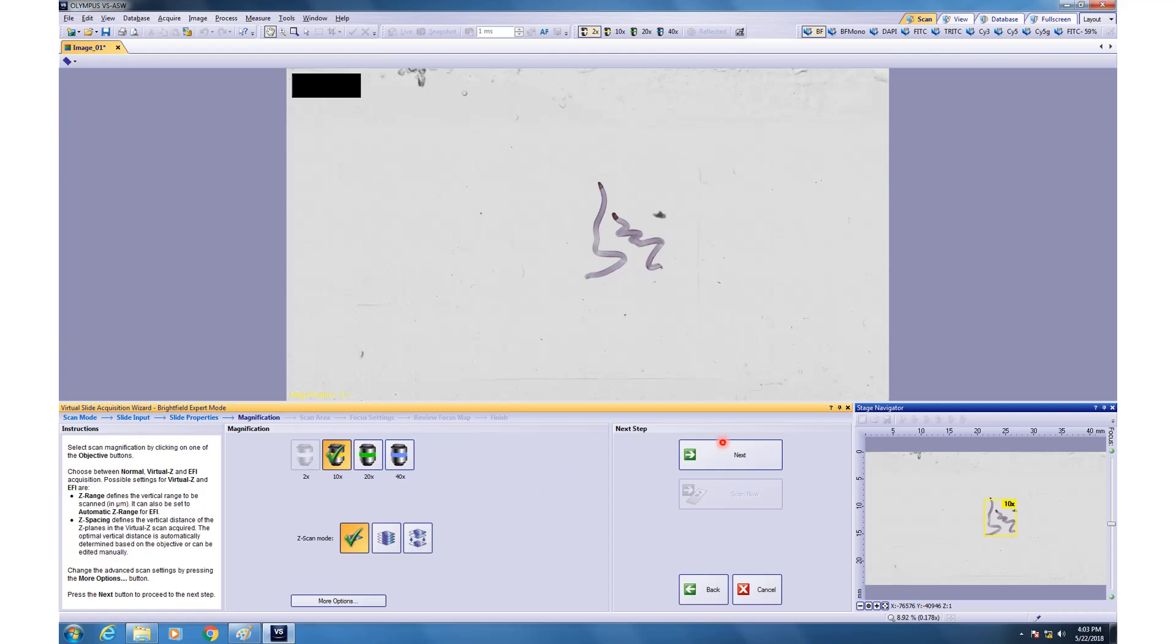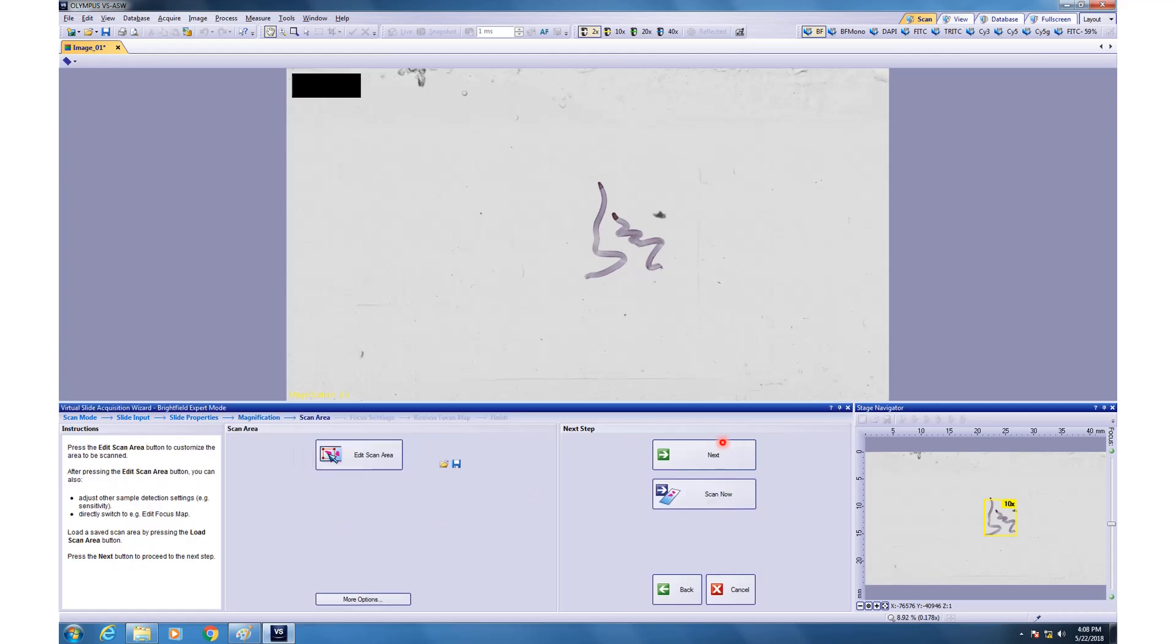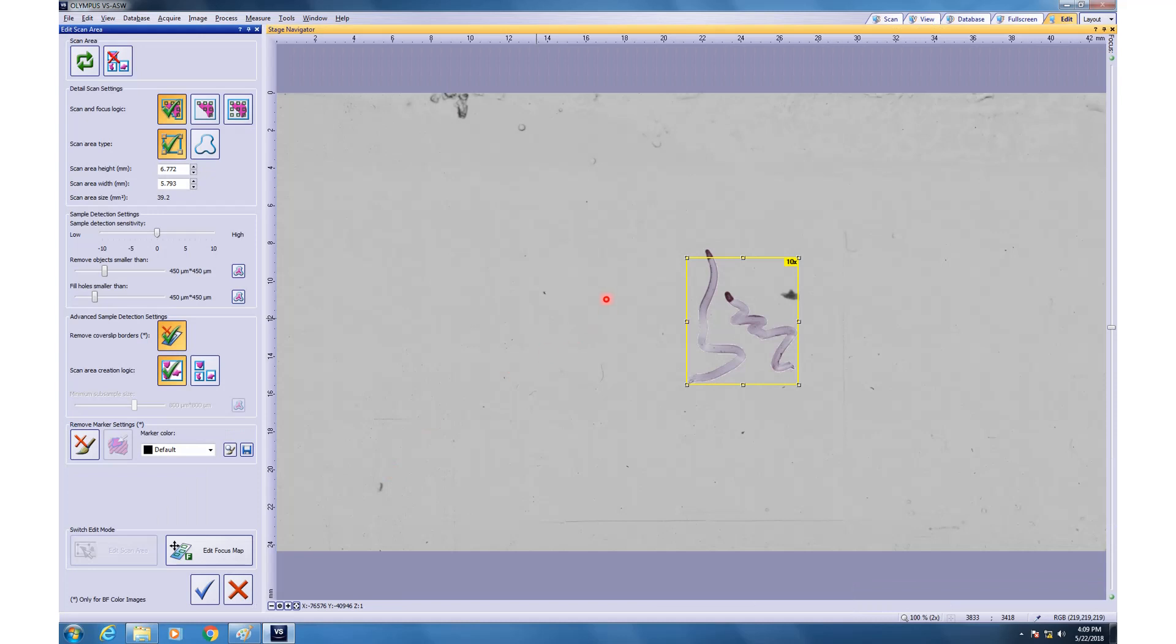After this you click next. As you can see that the software has done pretty good job in identifying the object but I am not happy with the selection, I would like to edit it. So, I would edit the scan area. If I click that, now I can change the box size, I can add more boxes or whatever. So, suppose I could also image here and here and everywhere else if I want to by dragging and creating new boxes. This is the kind of focus logic it will be following. Right now, it is going to only image the object here. You can see very thin white line here means it has actually done a very good job in sample detection. In case your sample detection is not very good, you can actually go for this option or this option where it is going to do a brute force method. It is going to image the entire thing.